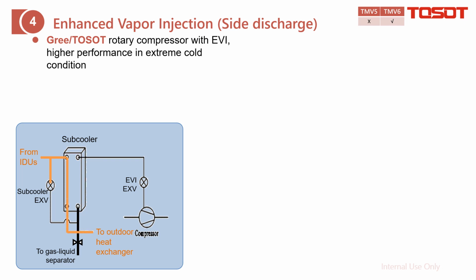Then the refrigerant from the indoor unit, actually it already becomes liquid, and then this liquid will flow through to the outdoor unit heat exchanger. However, a partial refrigerant just gets into this subcooler EXV and gets metering. Then we will make this part inject to the compressor by getting through this subcooler. The purpose of it is just to ensure this injection amount is completely vapor.